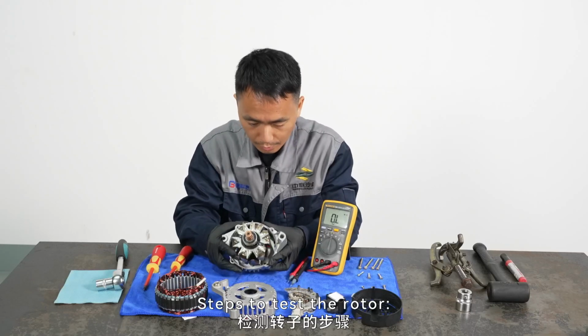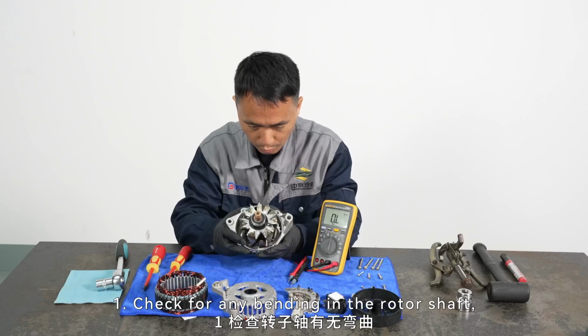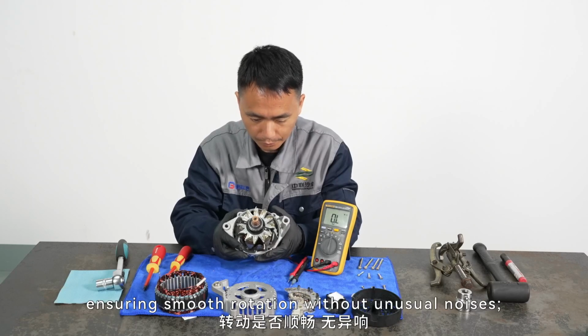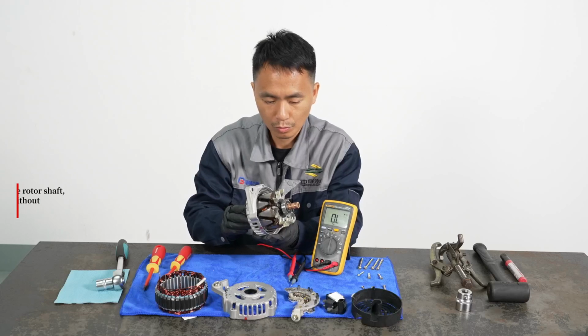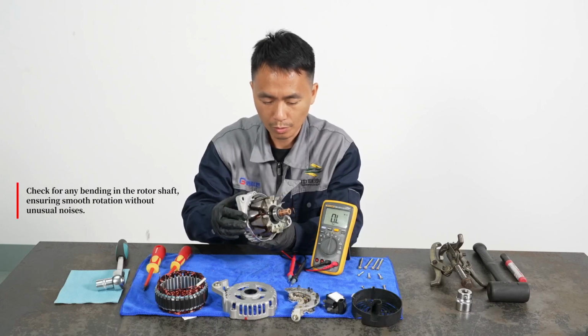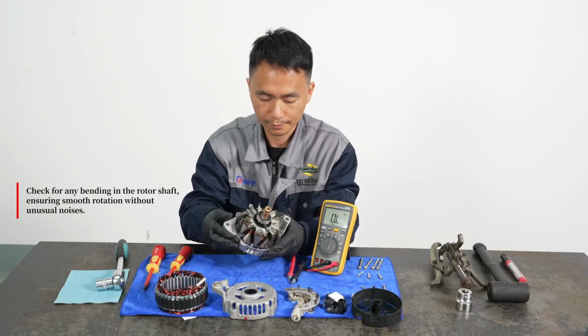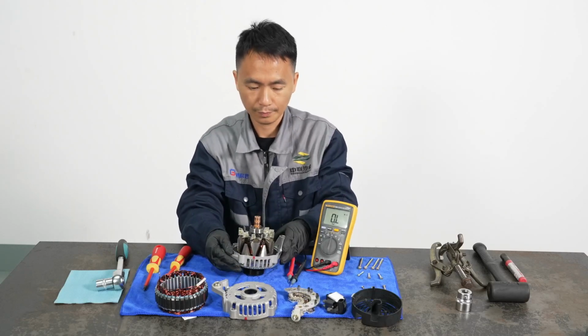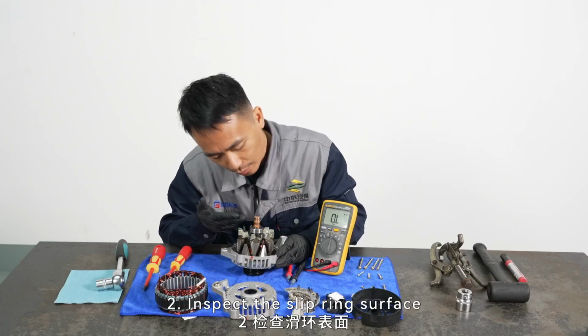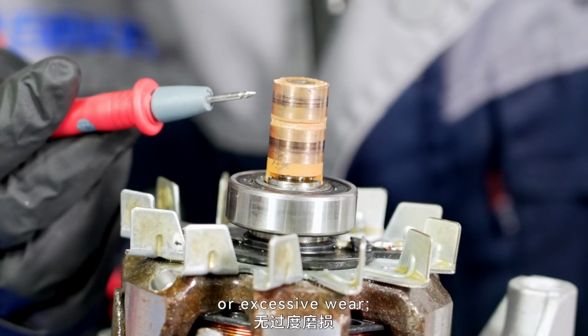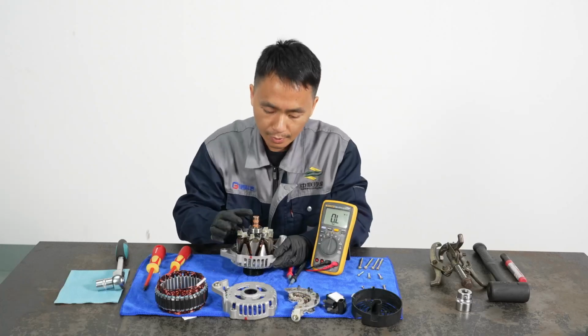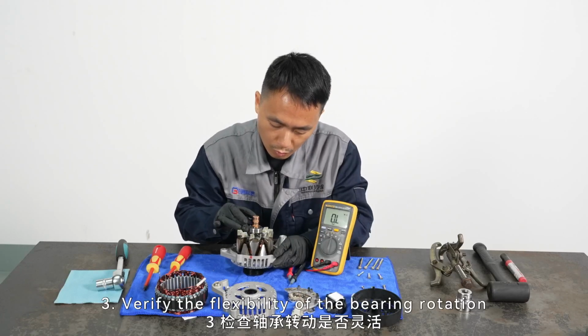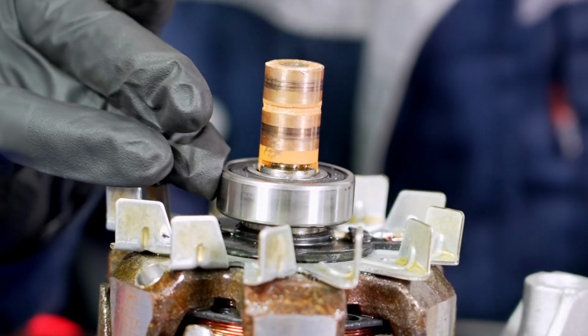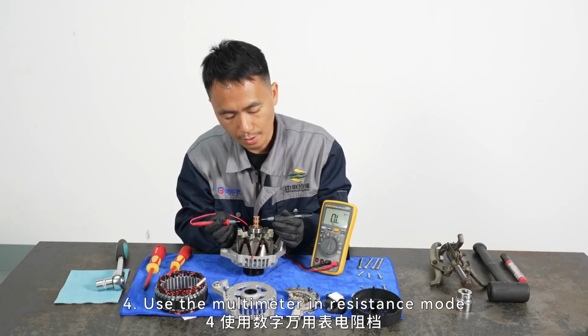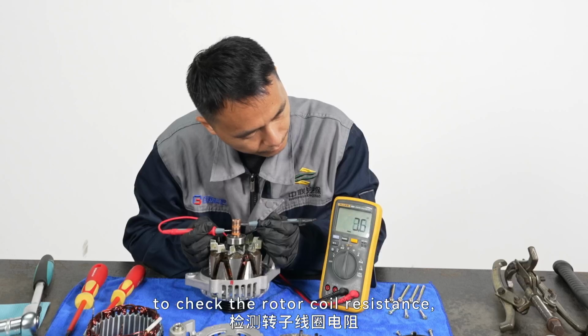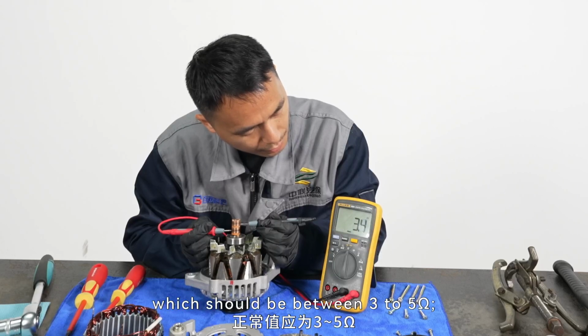Steps to test the rotor. 1. Check for any bending in the rotor shaft, ensuring smooth rotation without unusual noises. 2. Inspect the slip ring surface for smoothness, absence of burning, or excessive wear. 3. Verify the flexibility of the bearing rotation without any sticking. 4. Use the multimeter in resistance mode to check the rotor coil resistance, which should be between 3 to 5 ohms.